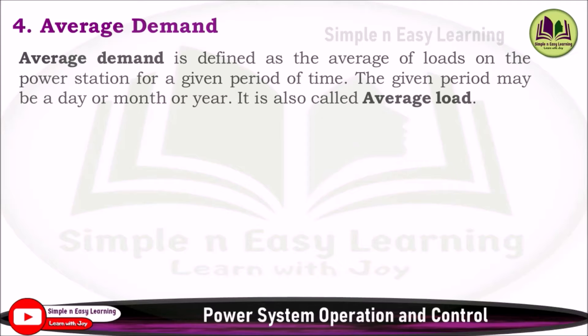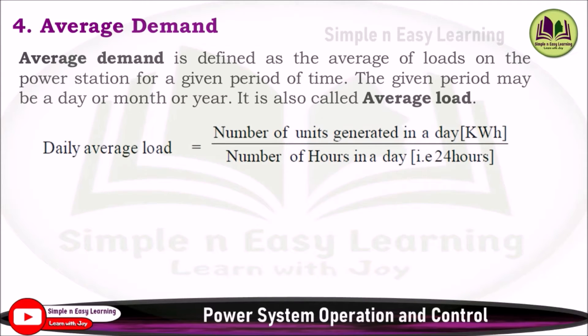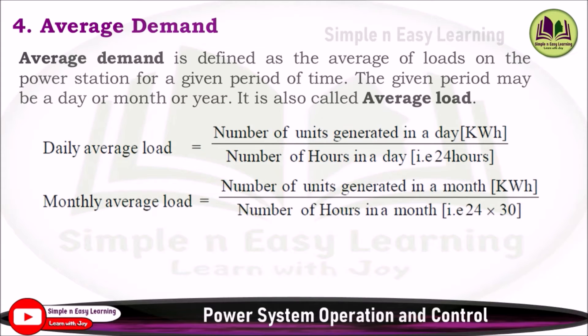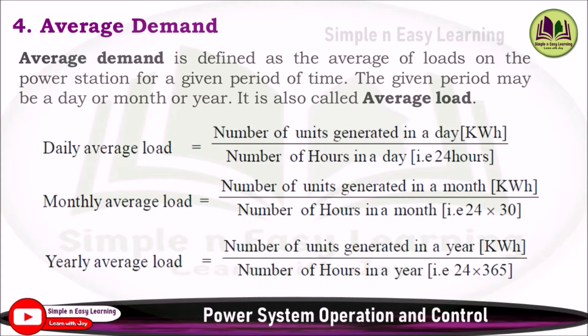Fourth: average demand, also called average load. It is defined as the average of loads on the power station for a given period of time — a day, month, or year. Daily average load = units generated in a day / 24 hours. Monthly average load = units generated in a month / (24×30) hours. Yearly average load = units generated in a year / number of hours in the year.